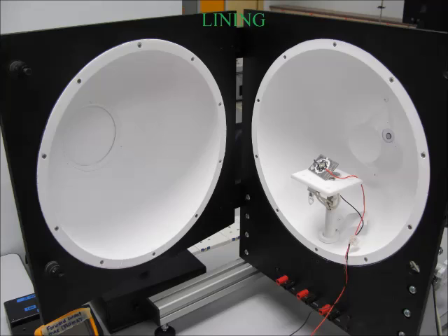Parts and components. Lining of the sphere. The optical properties of the lining affects accuracy. Different coatings are used for visible, infrared, and ultraviolet wavelengths. One point that should be taken into consideration is to avoid using high-powered light sources, as it might damage the lining.